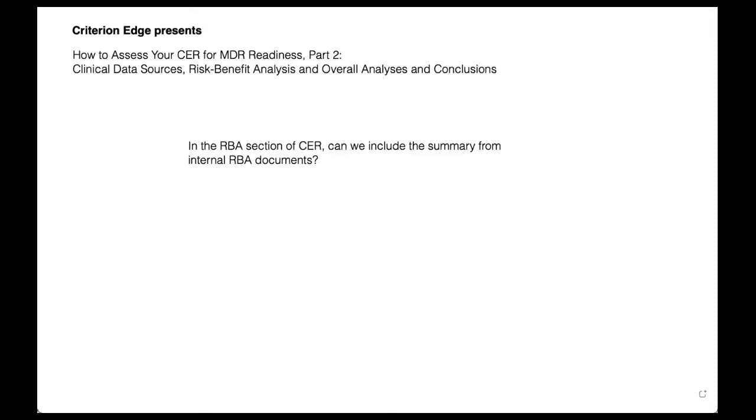It exists in its own world, and all data within and all conclusions and analyses that are housed within the CER must be analyzed and written within the construct of the CER and those GSPRs and those outcomes and those safety acceptance criteria. So if this is to mean that there's somewhat of a cut and paste from your internal RBA over to the summary of the CER, be very careful. That will not really fly because it may not be relevant.